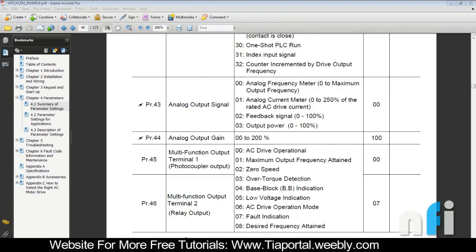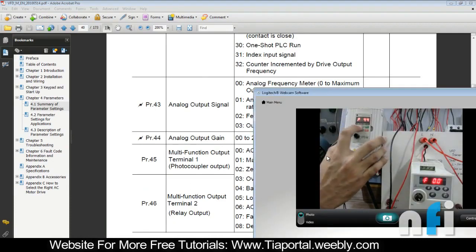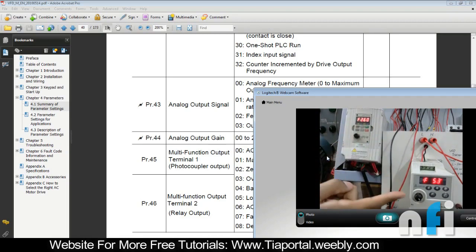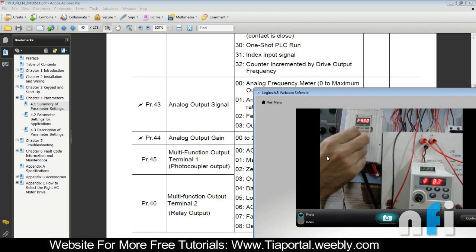Now let's try the second case — setting the gain to 200%, which is the maximum range. Go to parameter 44 and set it to 200%. Running the drive now: if the master is at 2.6 Hz, the slave shows 5.0 Hz. That's twice the input. If I take the master to 25 Hz, the slave will move to 50 Hz.